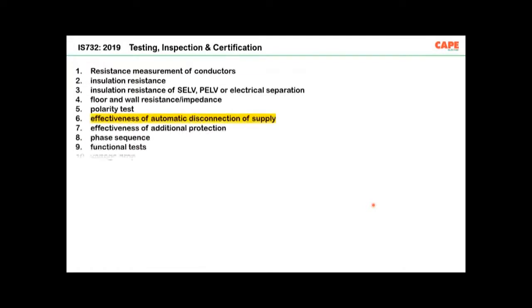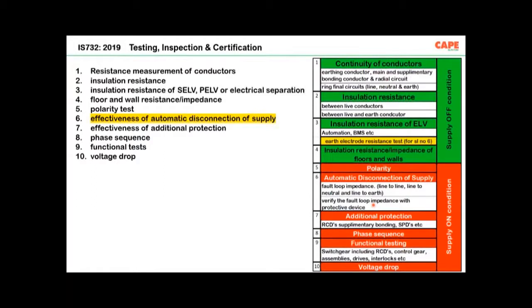Then the second: what testing is required in a modern installation? IS 732 2019 recommends 10 different kinds of testing, and one of them, number 6, is effectiveness of automatic disconnection of supply. What it means is, for getting fire protection and shock protection, you are supposed to disconnect your supply, for which you must ensure that your device is able to disconnect within a certain time by making this particular test. So basically, modern electrical installation standards are asking for 10 different tests. Out of these 10, 4 are in supply off condition and 6 tests are in supply on condition.